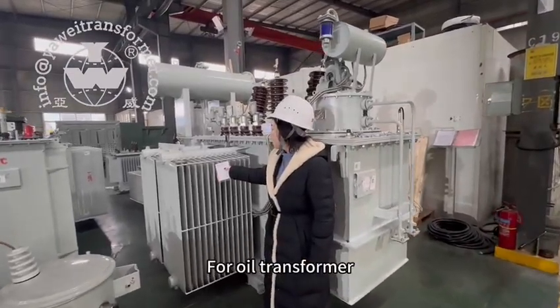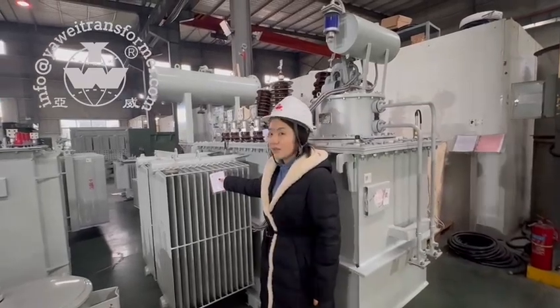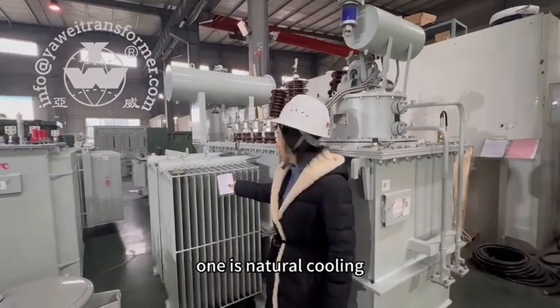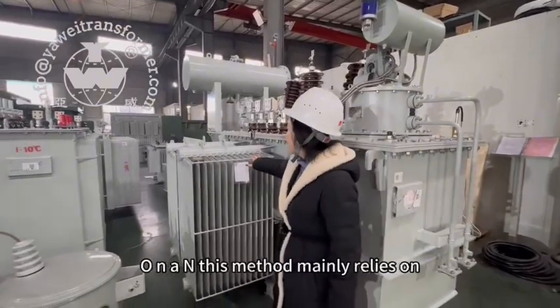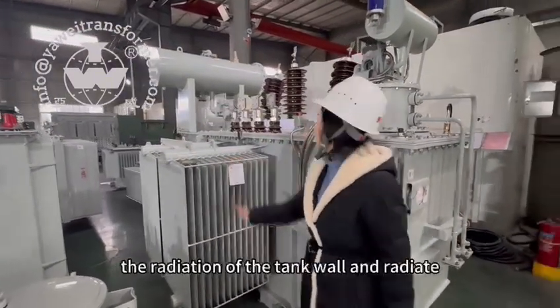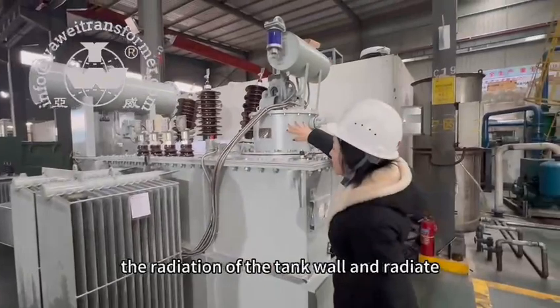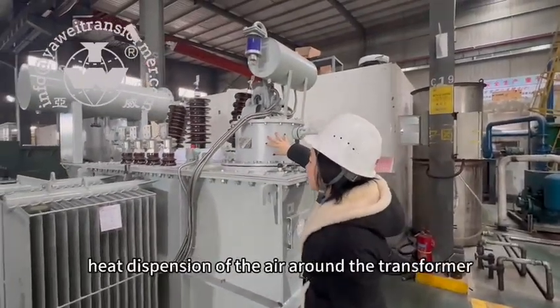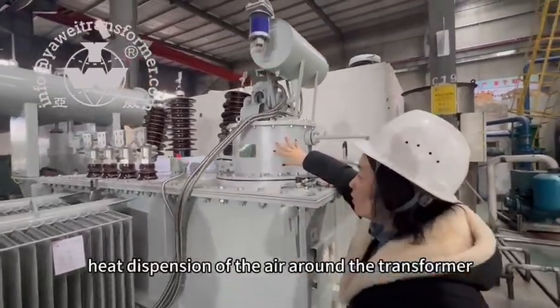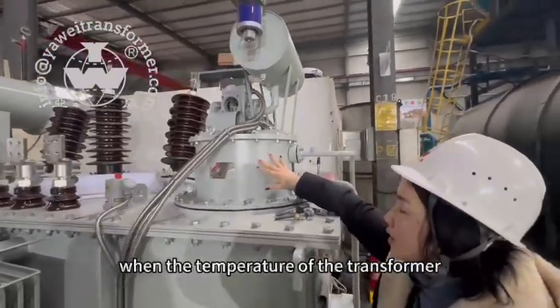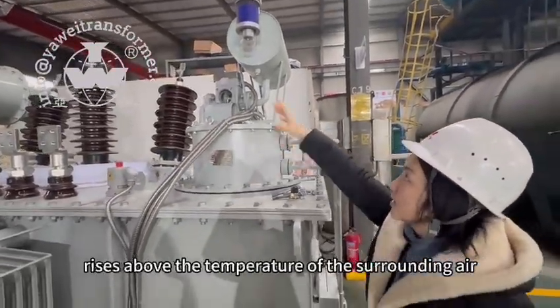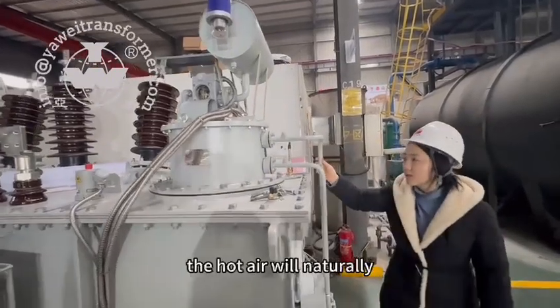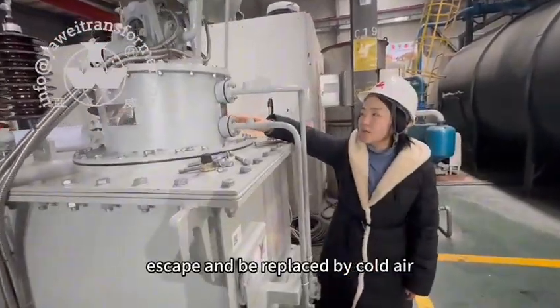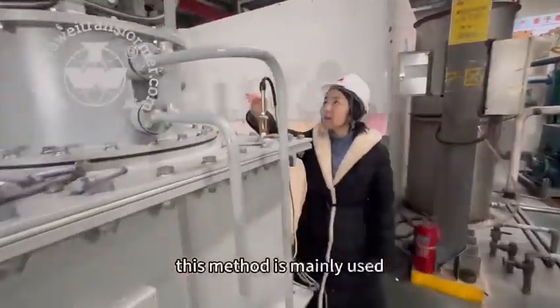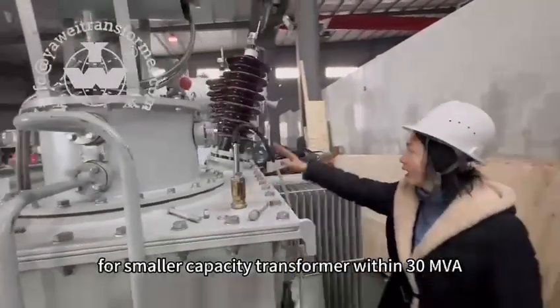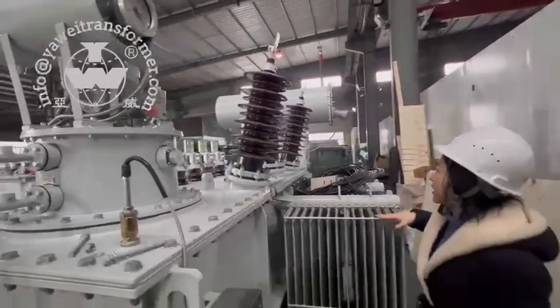For oil transformer, we have two cooling methods. One is natural cooling, ONAN. This method mainly relies on the radiation of the tank wall and the natural convection heat dispersion of the air around the transformer. When the temperature of the transformer rises above the temperature of the surrounding air, the hot air will naturally escape and be replaced by cold air. This method is mainly used for smaller capacity transformers within 30 MVA.